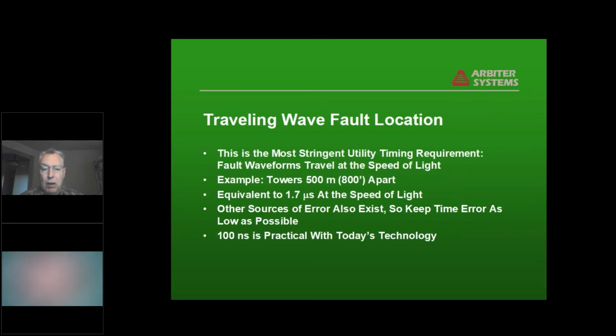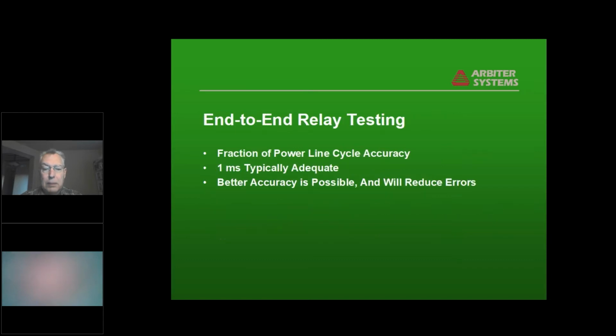And traveling wave fault locations, I mentioned, basically 1 nanosecond per foot, roughly. And so the more accurate the time is, the more accurately you'll know where the fault was. And 100 nanoseconds, which is equivalent to 100 feet difference, which will get you down to about 50 feet error on the fault location, is practical with today's technology. And so that makes traveling wave fault location a practical thing to do. And it's, as we said earlier, very useful to be able to know where to send the crew out to fix a line that's down or whatever's happened.